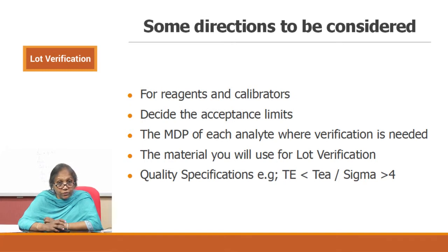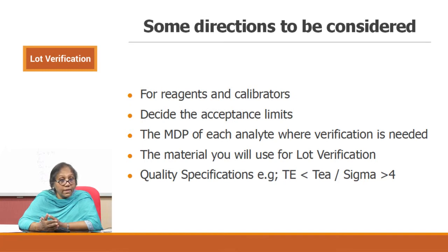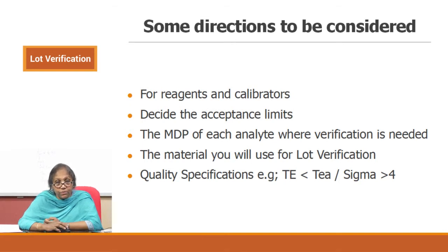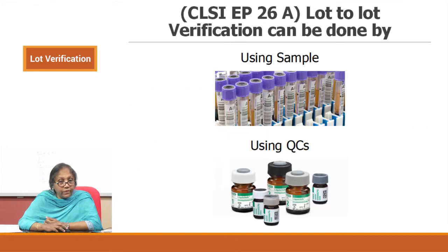The material you will use for lot verification — generally lot verifications are done using samples, but it can be done using quality controls also. Finally, you need to say what your acceptance criteria are. Do you want to put quality specifications like total error (TE) and sigma into your acceptance testing format? All these things should be written in your QSP.